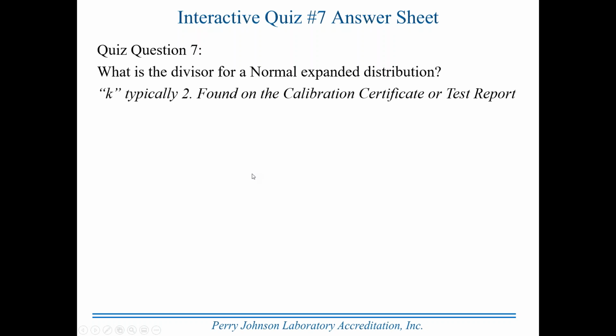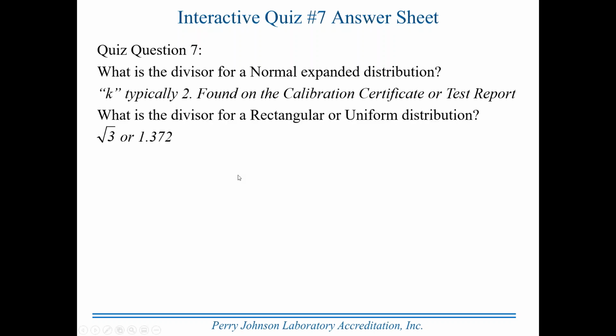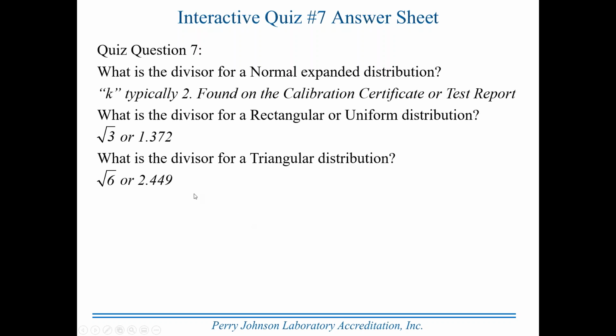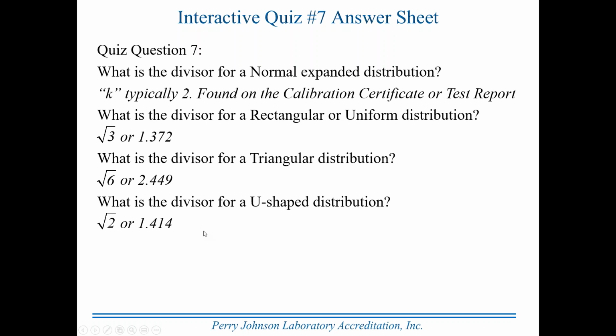All right, here's the answer sheet. I want to show you here that K is typically 2. We've talked about that many times, and it's found on the calibration certificate or test report. That's important to remember. The divisor for the rectangular is the square root of 3, or 1.732. The divisor for the triangular is square root of 6, 2.449. And for the U-shaped distribution, it was a square root of 2, 1.414.